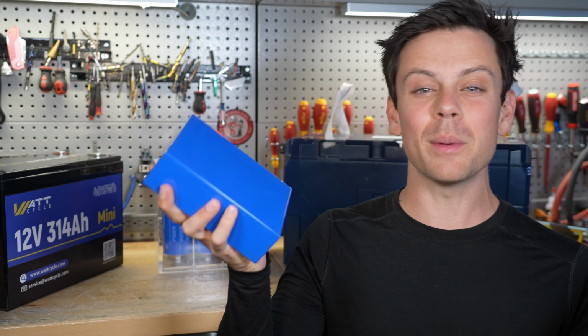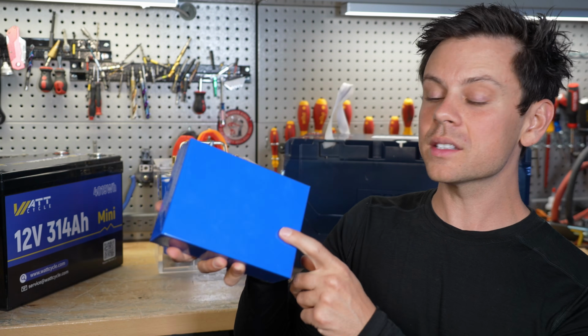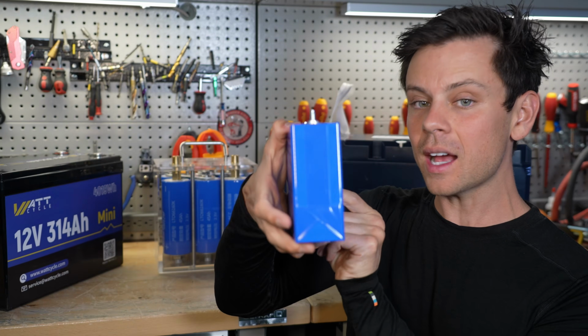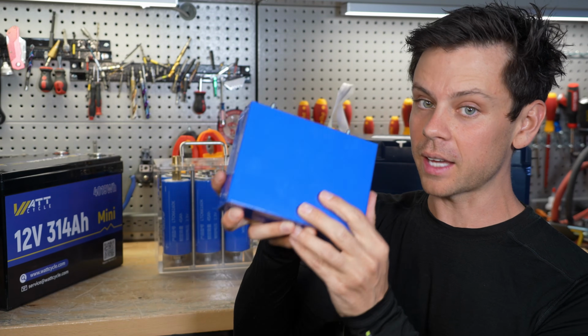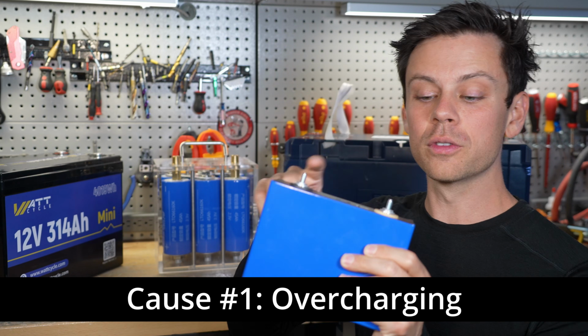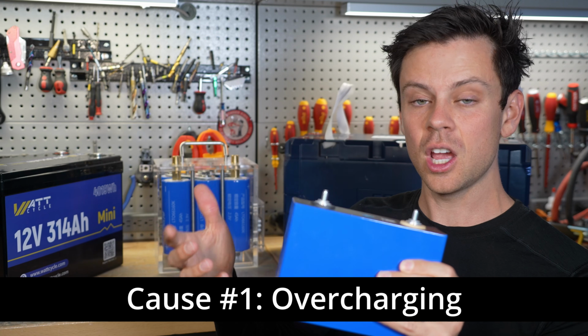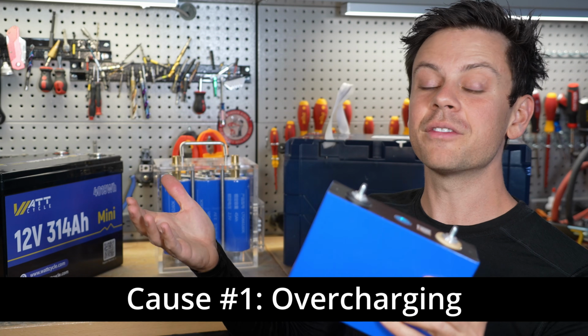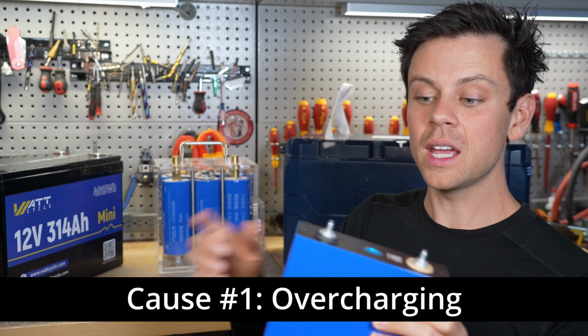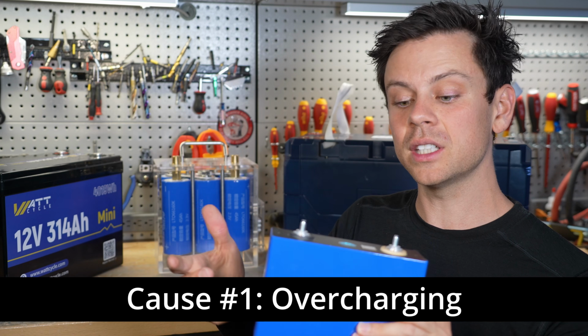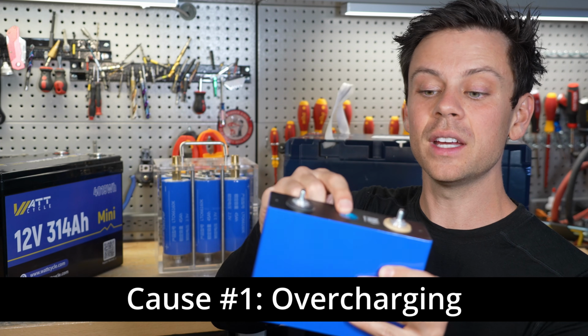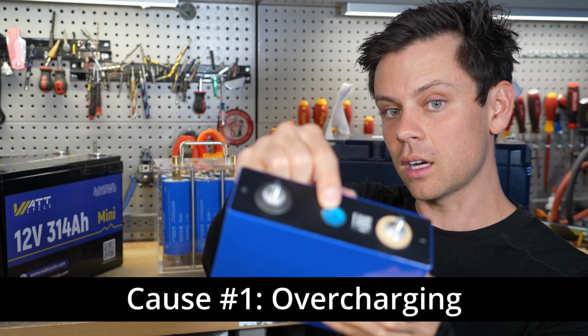So first, let's talk about failure mechanisms. What causes a healthy cell with no gas inside to create flammable gases? First is overcharging with high voltage. Usually there's a BMS, but if that fails and you have a shorted FET, the cell can be exposed to high voltage, create gas, and vent from the overpressure relief valve on top.